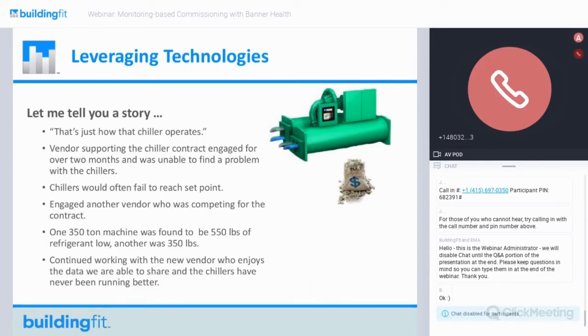We reached out to a new vendor and asked them to review the conditions of the 350-ton chillers. One of those was found to be 550 pounds of refrigerant short, and another was 350 pounds short. After these issues were corrected, along with a handful of other issues, we saw about a $20,000 per year savings in performance on those chillers.